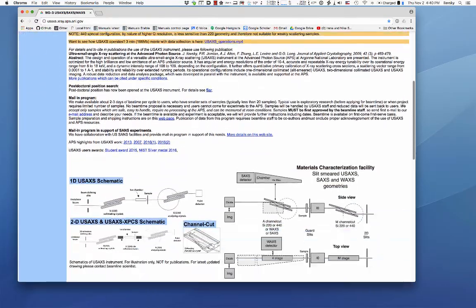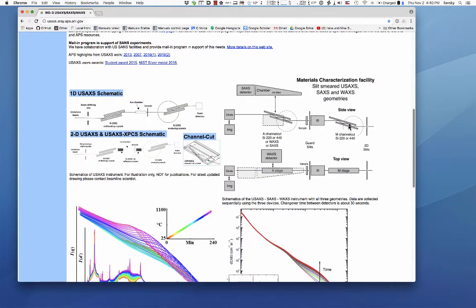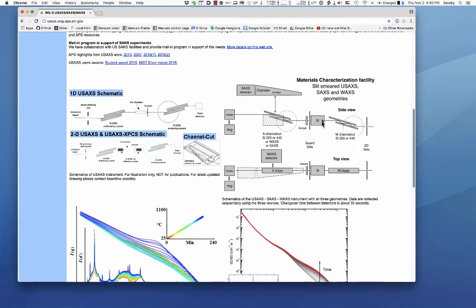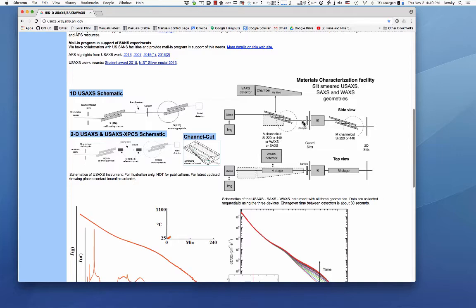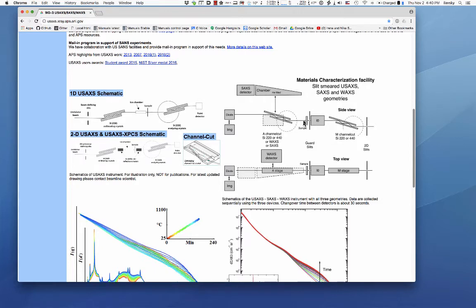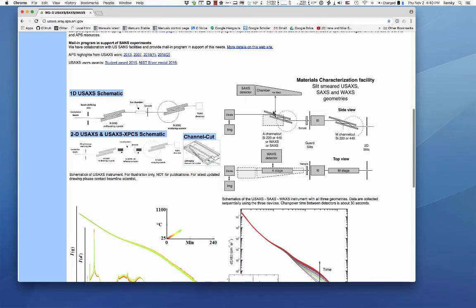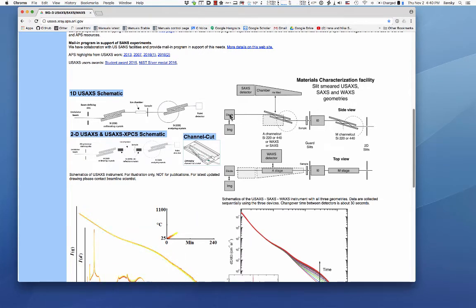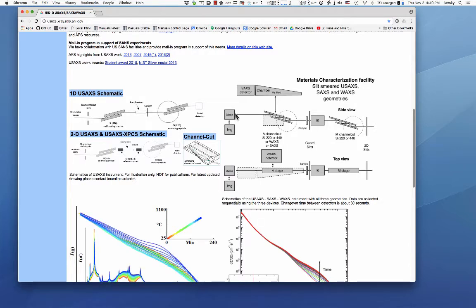Basically it's an instrument — shown here as a sketch — which uses a complicated Bonse-Hart setup where we have two parallel crystals, an artificial channel-cut, used to collimate the beam. There's some optics, a sample, and when the beam passes through the sample it contains a small angle and wide angle scattering component. To analyze that we have a channel-cut crystal — that's the USAXS instrument — and a detector which in our case is a photodiode. As we rotate this second channel-cut crystal, we collect intensity on the photodiode as a function of angle, scanning the ultra small angle and small angle range.